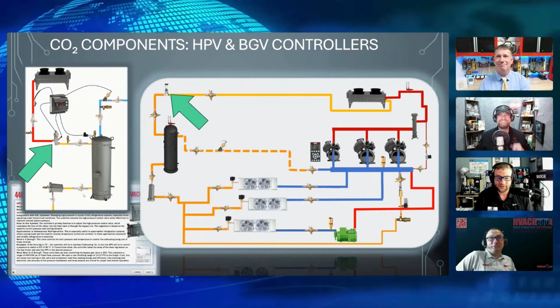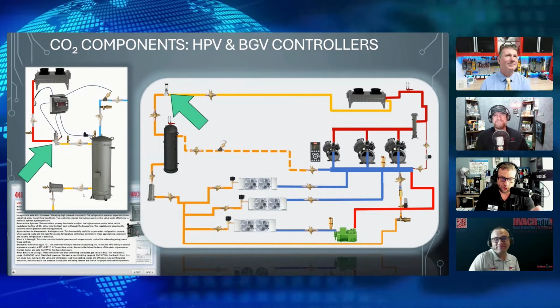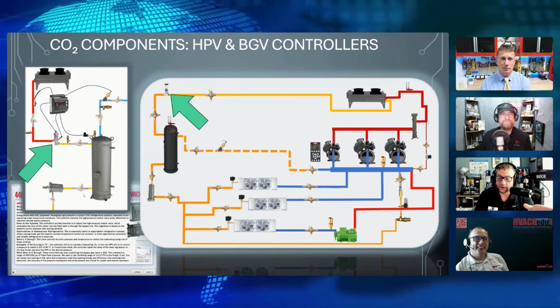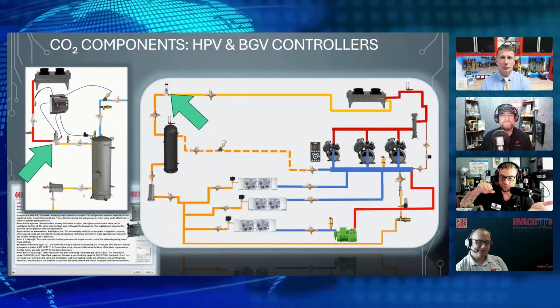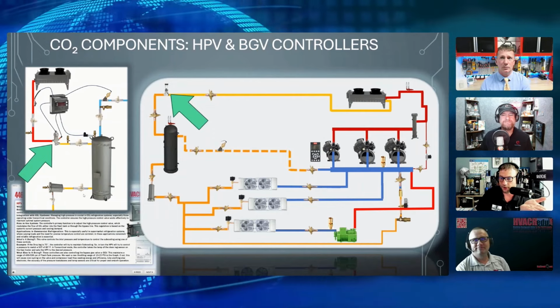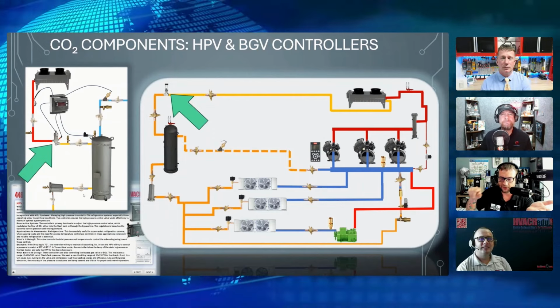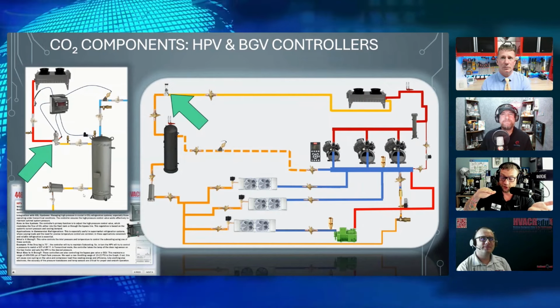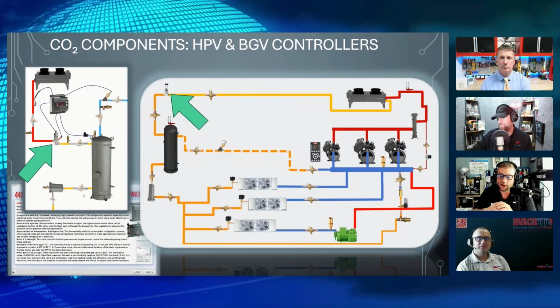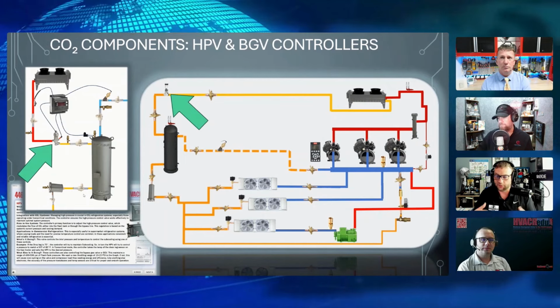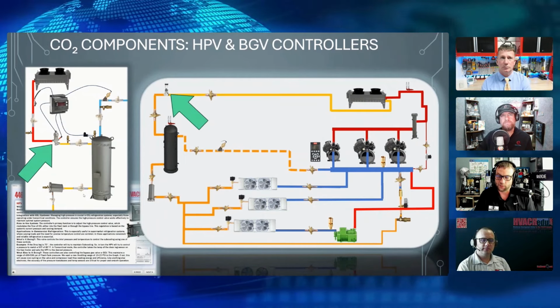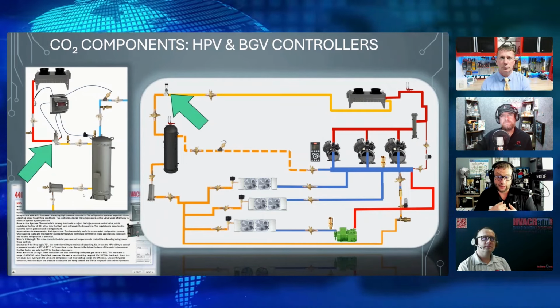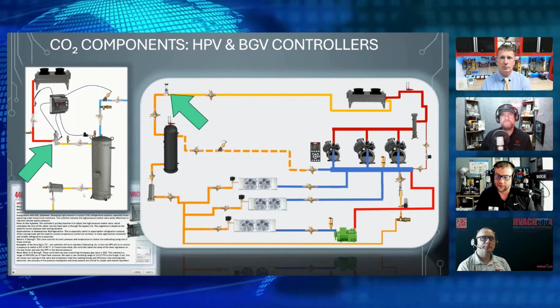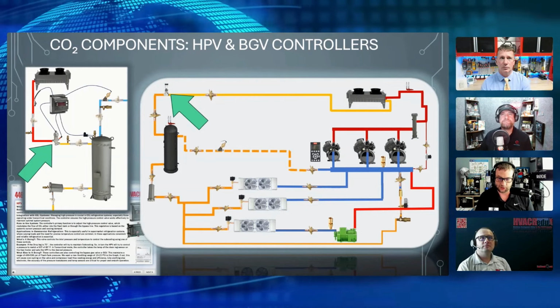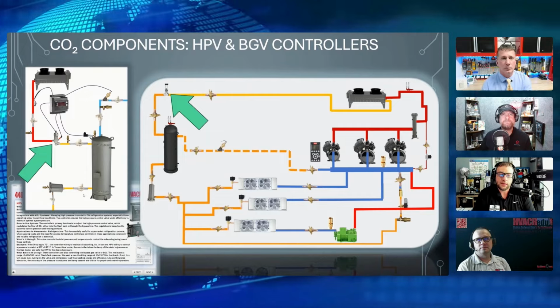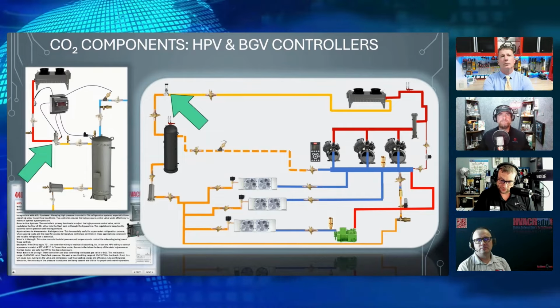It was pretty interesting. So once again, when it takes the drop leg temperature sensor at that point, it'll potentially try to just operate at that pressure. So if it's 90 degrees, I forget what the PT conversion is, what the algorithm is, but it'll try to maintain that saturated because we don't really care about trying to subcool anything at that point because it's impossible because we're in that transcritical form. So it just becomes a gas cooler, basically a desuperheater at that point, just trying to remove as much heat as humanly possible, right?